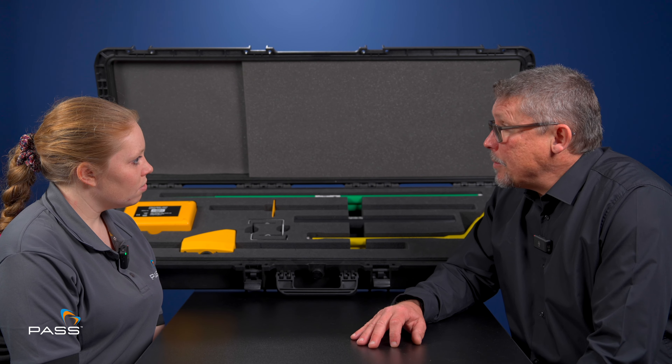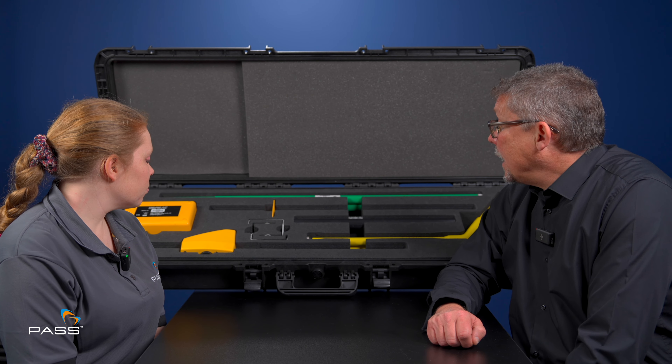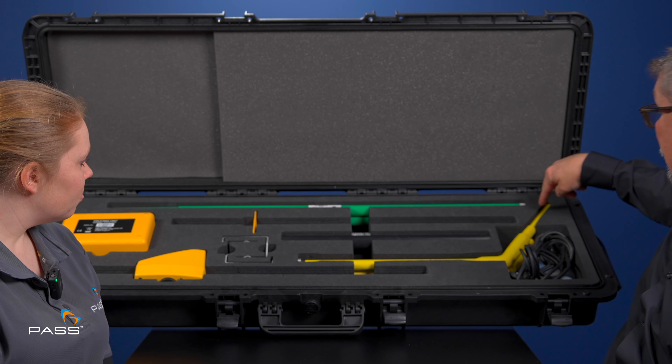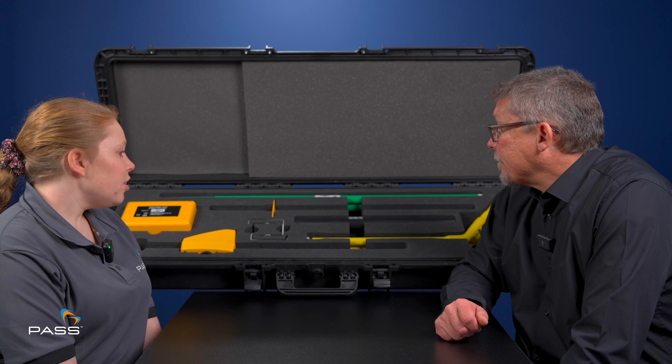We have a number of kits. We go from 3.3 through to 33 kV and you select the correct kit for the voltage at which you're working, because the display is on that part of the unit. On the display, the graduated analogue display will go up to the level at which you're working. So for example, if you bought an 11 kV kit, it will go to 15 kV. The kits themselves are designed wholly for AC systems. The whole thing about the kit is it's an all-in-one — everything you need. If you're working on overhead lines, you need extension poles — you have them here. If you're working on switchgear, we have the bent hand adapters to reach behind the switchgear to test and access the places where you'll be working. And the unit always comes with a proving unit to prove that the unit is working before use, and you prove it again at the end of the session, before you touch the line, so that you make sure you are truly on a dead system.